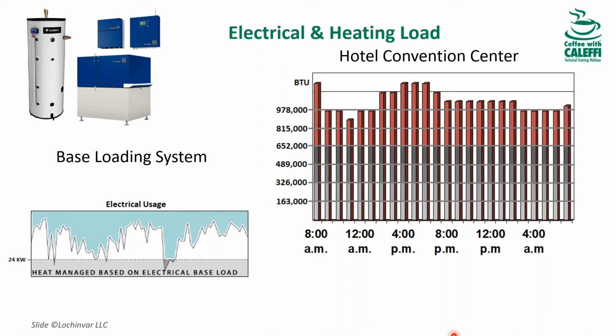Now, the interesting thing about micro-cogeneration is that it gives you some options. You can centralize and you can decentralize. What I mean by that is, take an example I like to give, a high school. You have a gymnasium and showers and everything, and you have a mechanical room. And you ask yourself, do I want to put all my cogens in the mechanical room, or do I want to put 2 of them out toward the gymnasium where I need the electricity and the hot water, and allow that to operate decentralized from the other 2 that are running the rest of the building, okay?